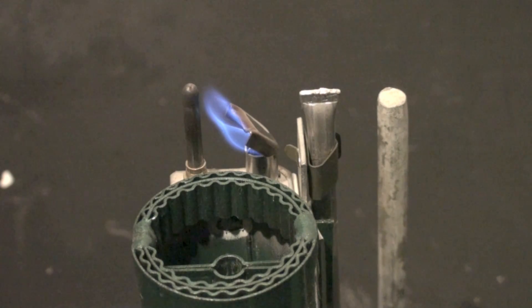It's not covering up the thermocouple like it should. So that one does not have enough flow. Now there's a pilot adjust on the gas valve. And I'll show you where that is.